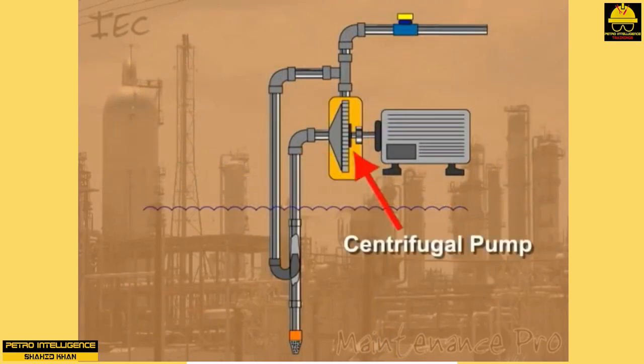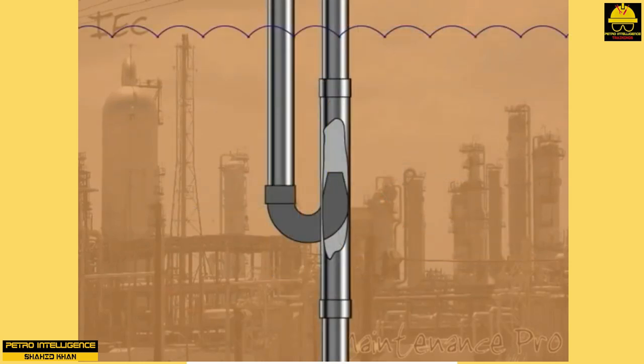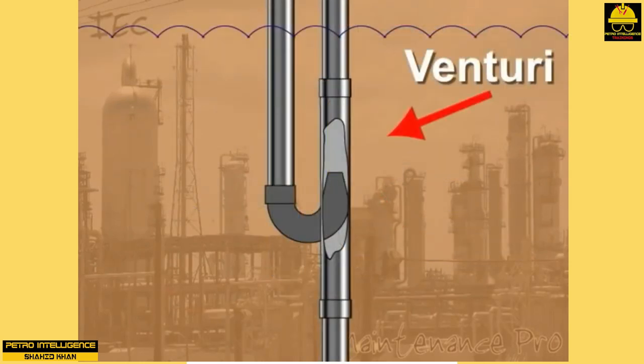During operation, water is forced back down the void between the center drop pipe and the outer casing. As water is pumped back into the well casing, the foot valve slams shut. A small opening in the jet provides access back to the suction of the pump. A Venturi effect occurs at the jet as pressure builds up in the casing.